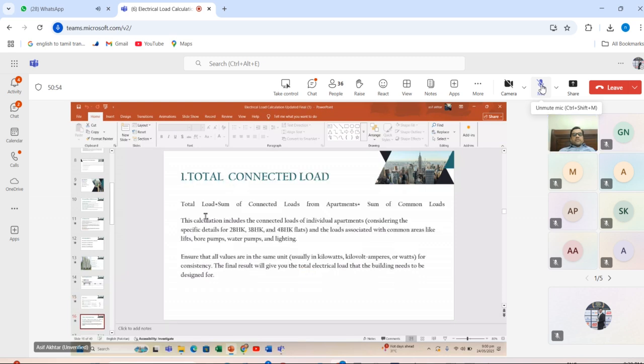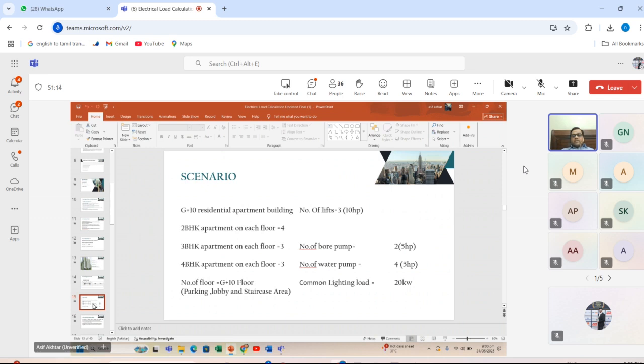Common lighting load is 20 kilowatt, for parking, lobby, and staircase area. Total connected load is the sum of connected load from apartments plus the sum of common loads. Common loads include the lighting load, the number of water pumps, and the number of bore pumps.